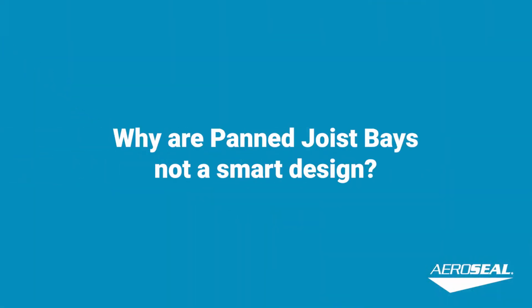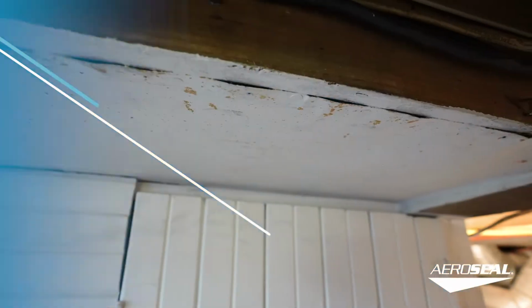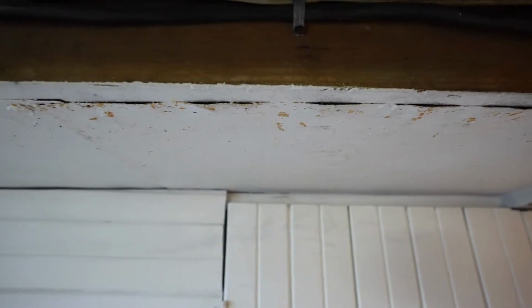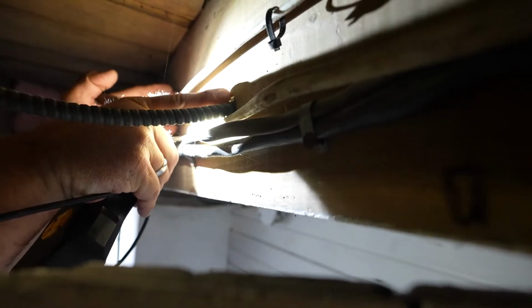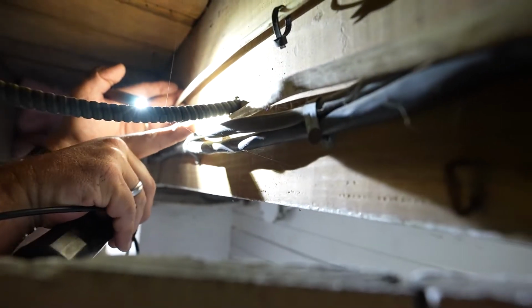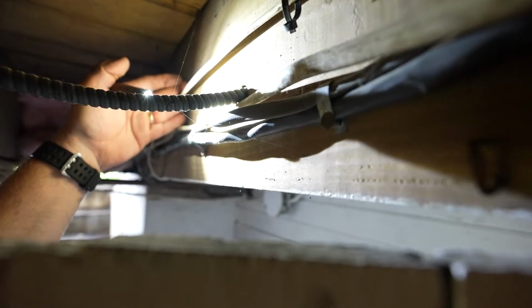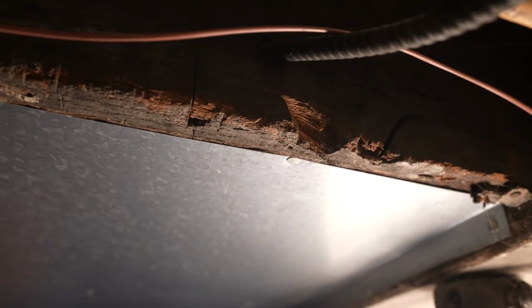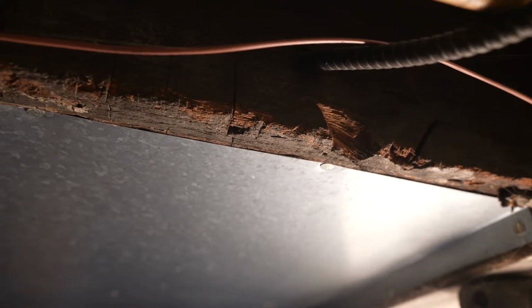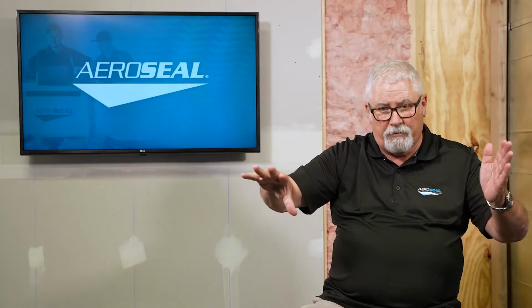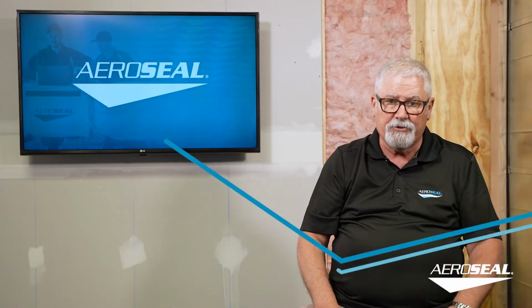So why are panned joist bays not really a smart design? Number one, they're not airtight. There are many holes by piping or wires that run through them. When they install the material, they don't get it tight, and they haven't sealed it using mastics. That's why in many parts of the country, codes now require us to use one solid piece of pipe - it could be square duct or round duct - but at least we start with a connection, so there's nothing allowing air to come in from around it wherever it goes through, which can then be drawn in by negative pressure.